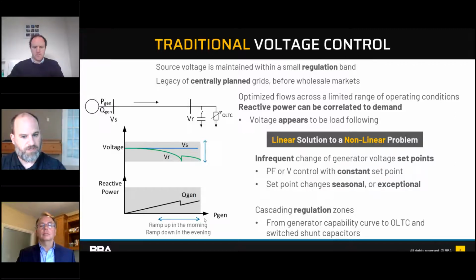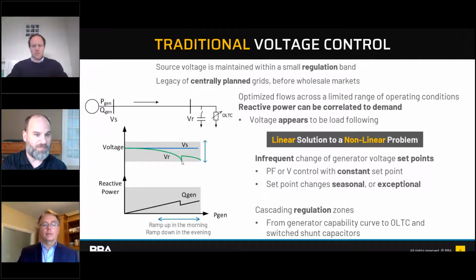And you get the voltage that starts to sag. Then all of a sudden there's your nonlinear relationship going down as voltage decreases, and boom, here's where you're fixing for your linearization. You've got these discrete actions that are things like your cap bank switching, your on-load tap changers, compensating for load. So you have these discrete actions that allow you to move back to your linearization point effectively around your linear control.